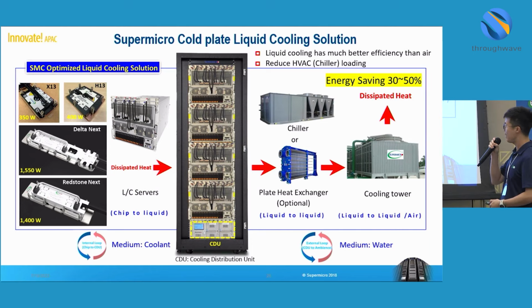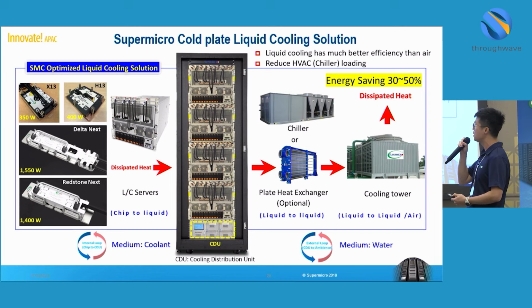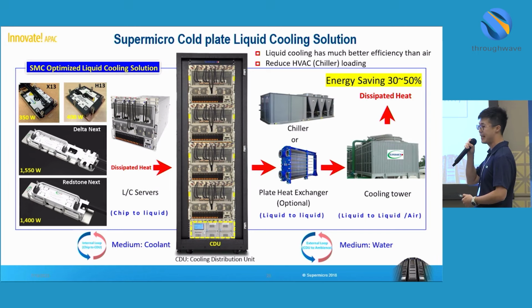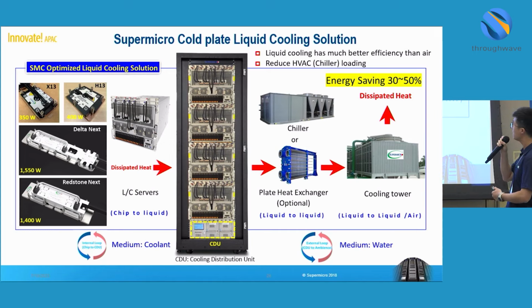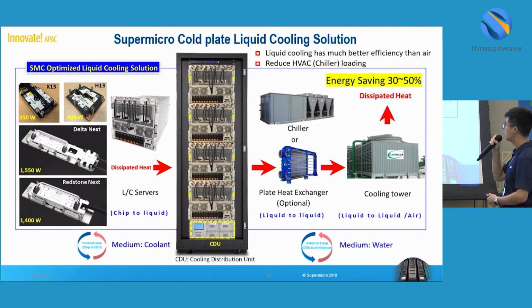On the left-hand side, there's an internal loop between the chip and the CDU. Supermicro designed the CPU and GPU cold plates, including the Delta Next and the Redstone Next. The rack can mount up to 4 Delta Next liquid cooling servers and connect to the CDU by the CDM.